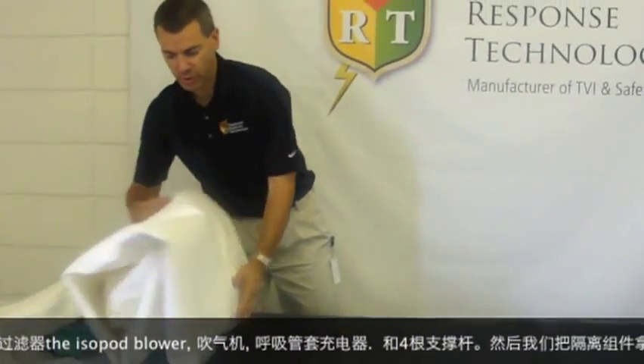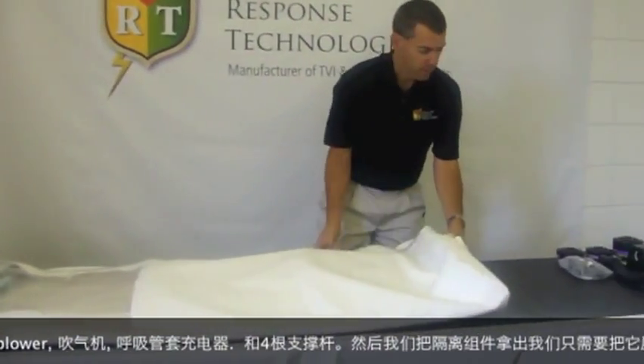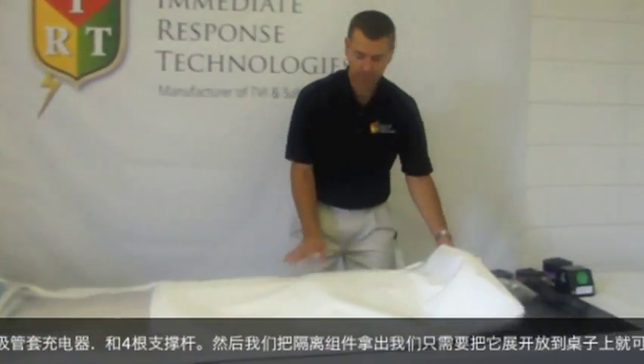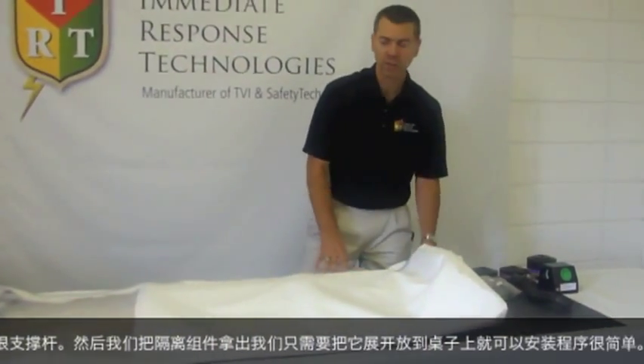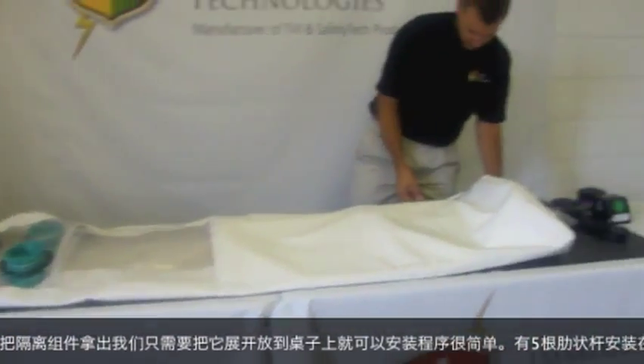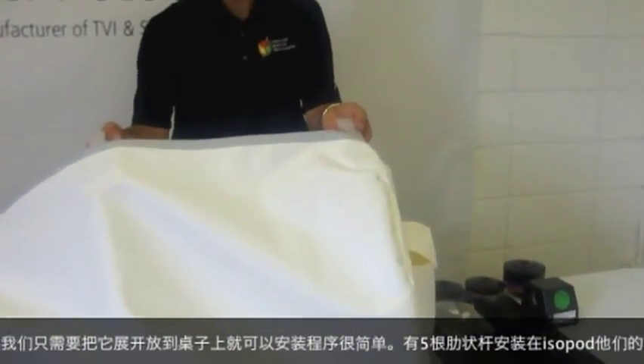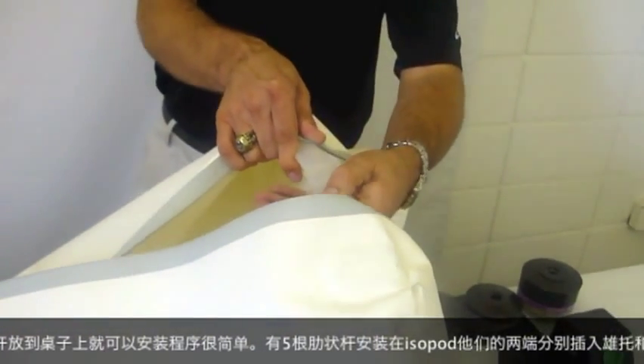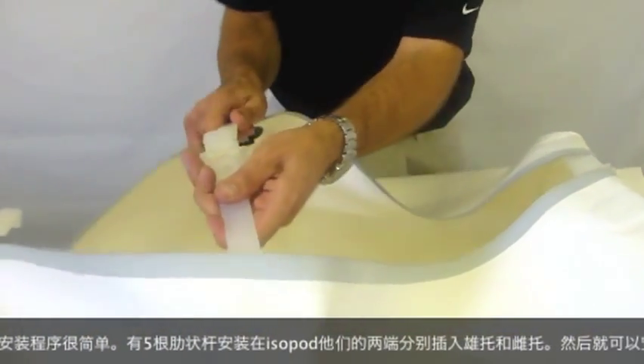We're simply going to unroll the unit. The isopod can be secured to a gurney if the unit that was purchased includes restraints, or it can just sit on a table. The assembly process is very simple. There are five ribs that extend across the isopod. You simply take both ends of the ribs and insert the male receptacle into the female receptacle. You repeat this for all five of the ribs.